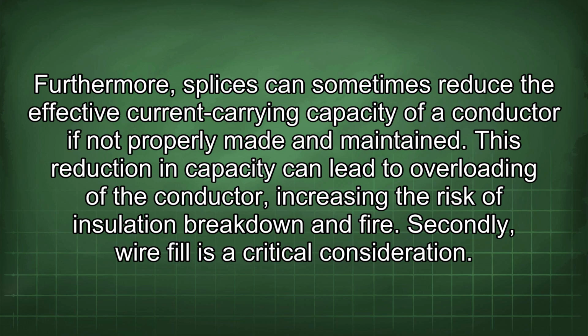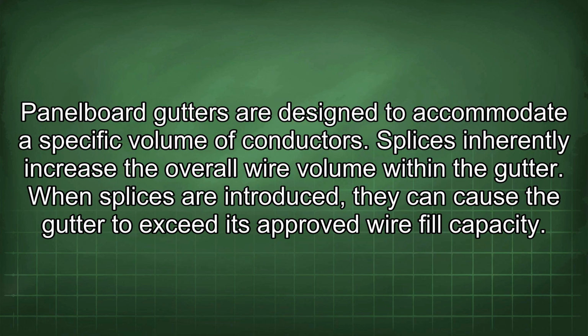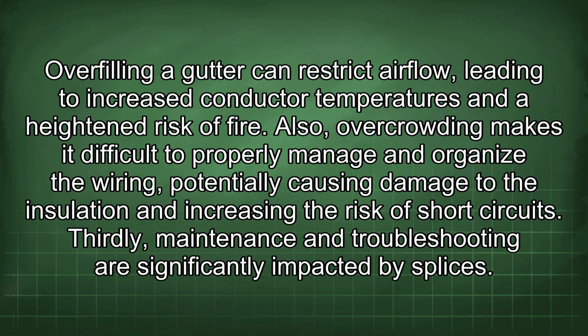Secondly, wire fill is a critical consideration. Panelboard gutters are designed to accommodate a specific volume of conductors. Splices inherently increase the overall wire volume within the gutter. When splices are introduced, they can cause the gutter to exceed its approved wire fill capacity. Overfilling a gutter can restrict airflow, leading to increased conductor temperatures and a heightened risk of fire. Also, overcrowding makes it difficult to properly manage and organize the wiring, potentially causing damage to the insulation and increasing the risk of short circuits.